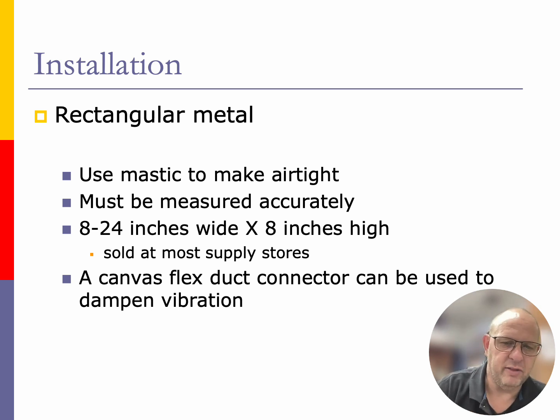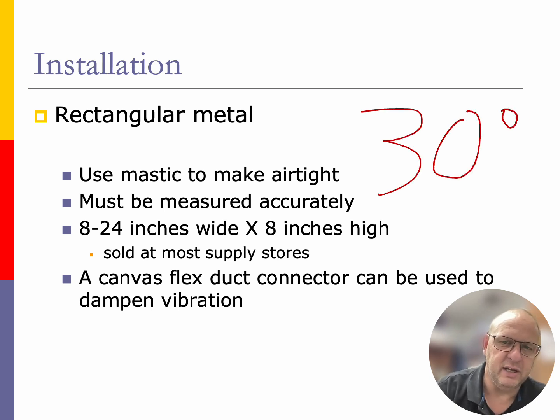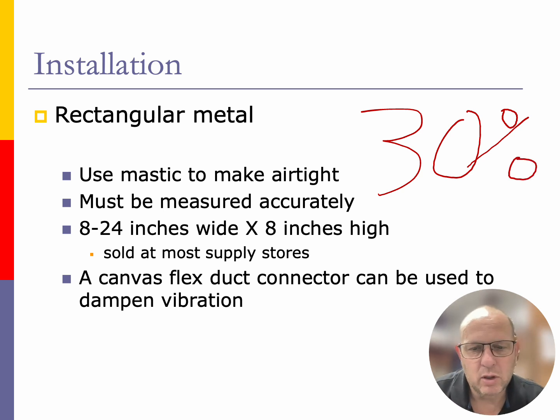30% of the air that we condition, if we don't seal our ductwork up, will be lost to the unconditioned space. So 30% of the air, if we're not sealing that ductwork up or we're not insulating that ductwork properly, could be lost to other conditions that we don't want to happen. So this would be wasted money, wasted energy that we're putting into unconditioned spaces in that environment. So it's important for us to seal that ductwork up with mastic.